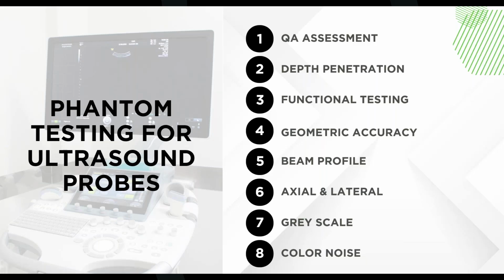So when you're running through and doing a quality assurance for ultrasound transducers, when our field service technicians go and do PMs, we're doing tests for each one of our transducers. A good ultrasound quality assurance program is a routine testing and checking and verifying that the ultrasound probe and transducer is performing correctly, safely, and consistently according to clinical and manufacturer standards.